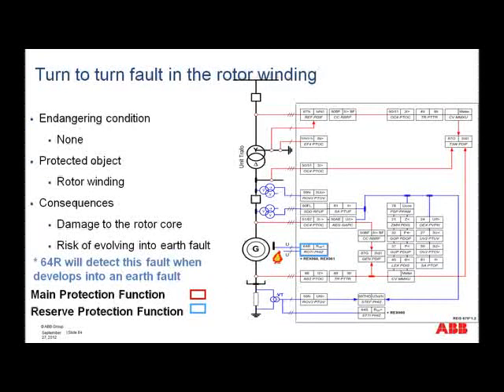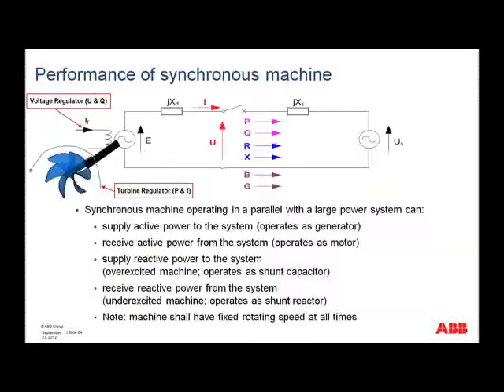Now if you had a turn-to-turn fault in the rotor winding, well, you could say that this would be detected when this develops into an earth fault. So there's really nothing that is detecting this until it becomes an earth fault. So this is shown in blue here. But should this turn-to-turn fault develop into an earth fault, then this injection principle would be able to handle it and detect it.